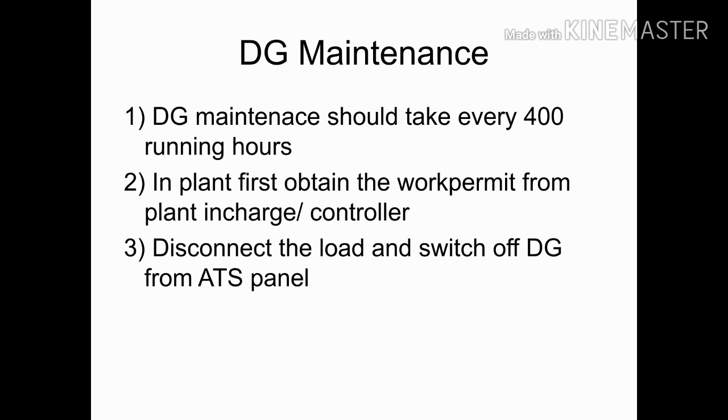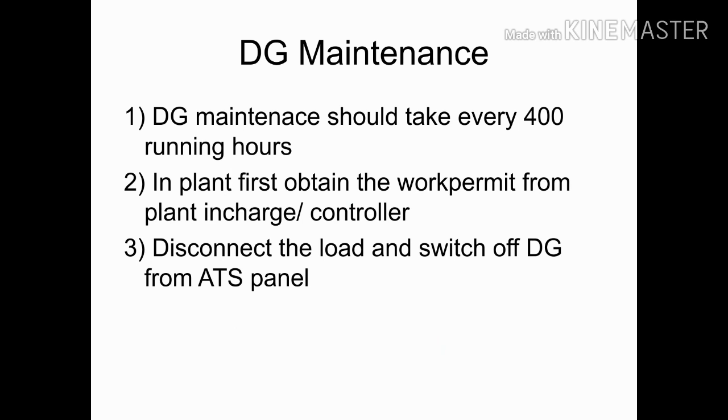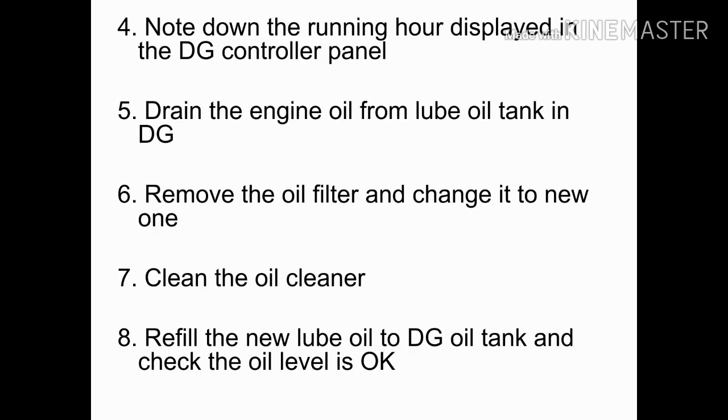After obtaining the work permit, disconnect the load from the diesel generator and switch off the diesel generator from the ATS panel. In most plants, the diesel generator is controlled by the ATS panel — ATS stands for Automatic Transfer Switch. Before starting maintenance, note down the last running hours displayed on the DG controller panel.